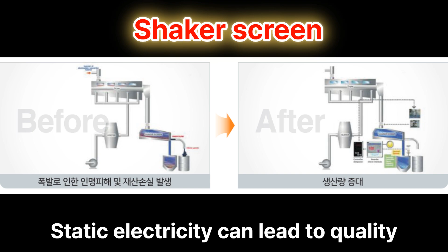Visible static electricity measurement is the key to preventing accidents. Actual measurement results show that static electricity exceeding 7,500 V is frequently measured inside the bag filter, indicating a very high risk of dust explosion. You can immediately check such risk levels and reduce them to below 2,000 V through a transmitter that can eliminate static electricity. In this way, prevention, measured in numbers, is a technology that protects lives.